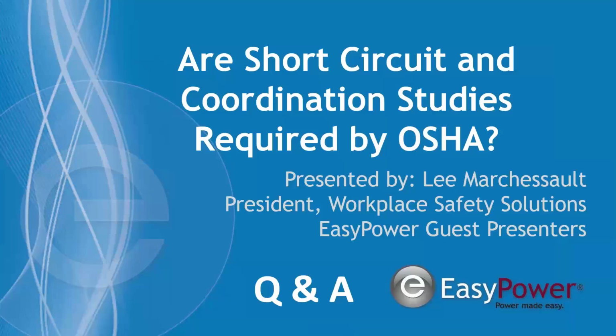The next question: you might want to mention that you can't coordinate breakers with instantaneous pickup if the fault current exceeds the pickup of the upstream device unless you use zone interlocking. Reducing the pickup of the feeder won't solve the problem. Good point. I think he covered it. Yeah, I think it's a good statement. Yes, absolutely.